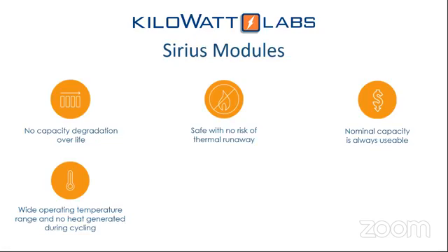And then the advantages that you get because there's no chemical reaction taking place: it's a straightforward electricity to electricity storage. You are not affected by heat. So Sirius operates very comfortably up to 55 degrees centigrade. The other real big advantage that you get for no chemical reaction is that Sirius does not generate heat when it's cycling. All chemical batteries, when they cycle between charge and discharge, generate heat. The faster you charge and discharge them, the more heat they will generate. So you need extra cooling and things like that.